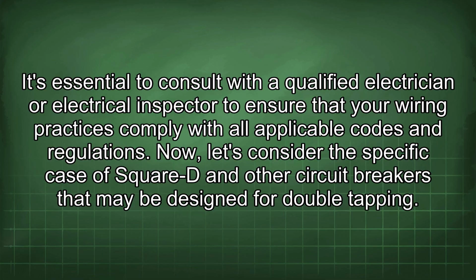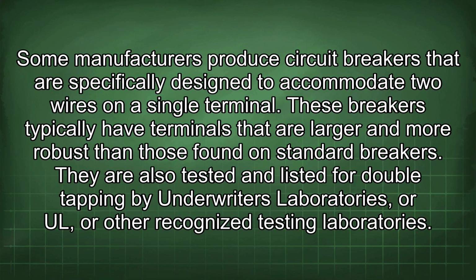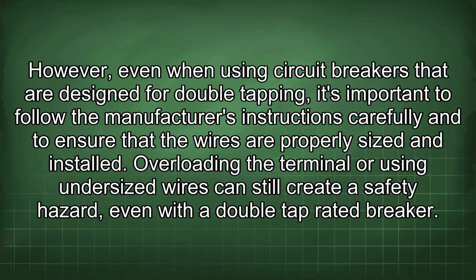Now, let's consider the specific case of Square D and other circuit breakers that may be designed for double tapping. Some manufacturers produce circuit breakers that are specifically designed to accommodate two wires on a single terminal. These breakers typically have terminals that are larger and more robust than those found on standard breakers. They are also tested and listed for double tapping by Underwriters Laboratories or other recognized testing laboratories. However, even when using circuit breakers that are designed for double tapping, it's important to follow the manufacturer's instructions carefully and to ensure that the wires are properly sized and installed. Overloading the terminal or using undersized wires can still create a safety hazard, even with a double tap rated breaker.